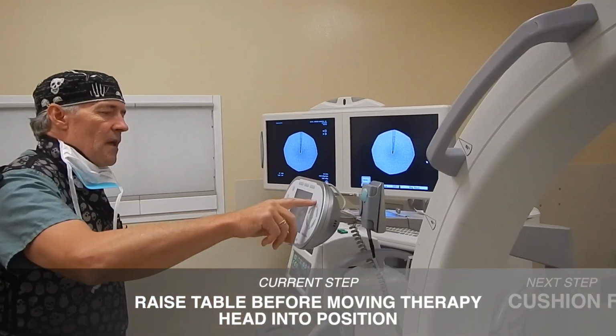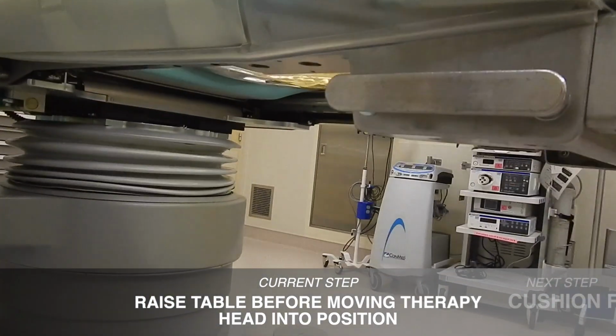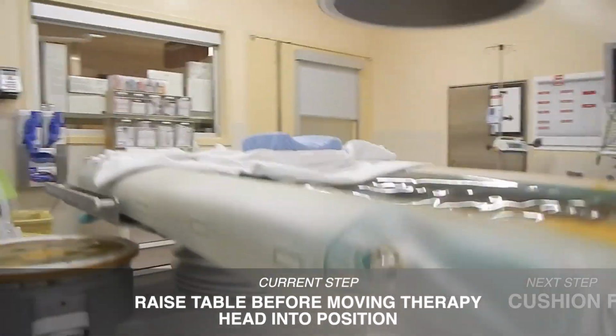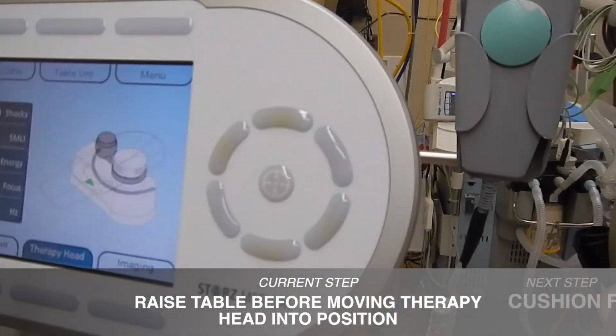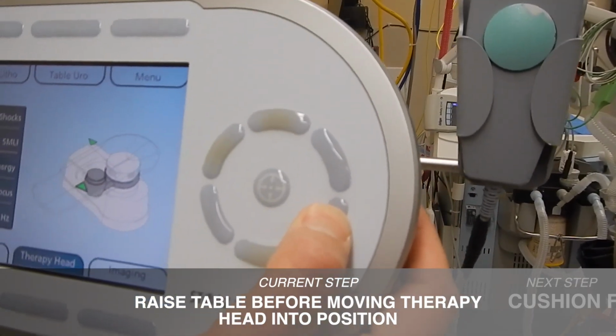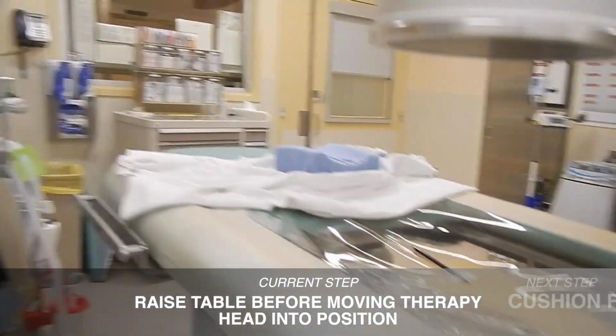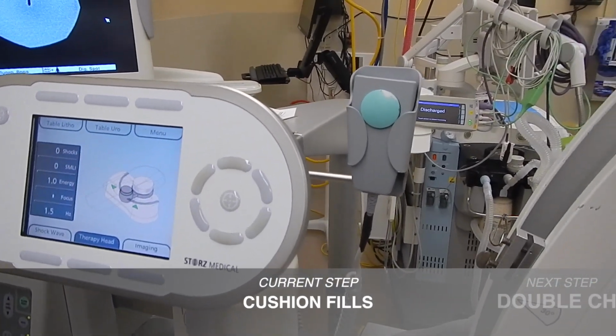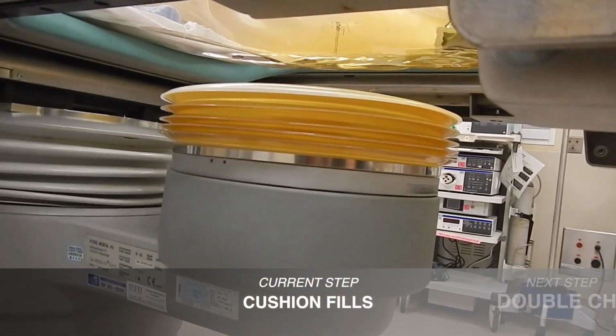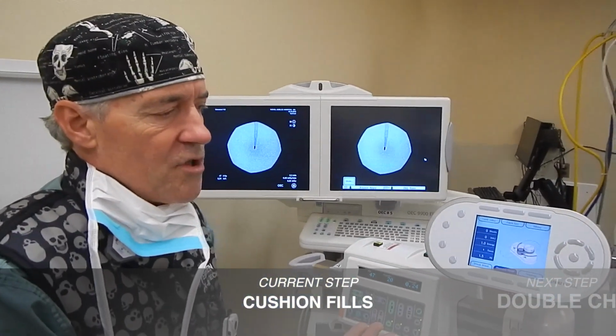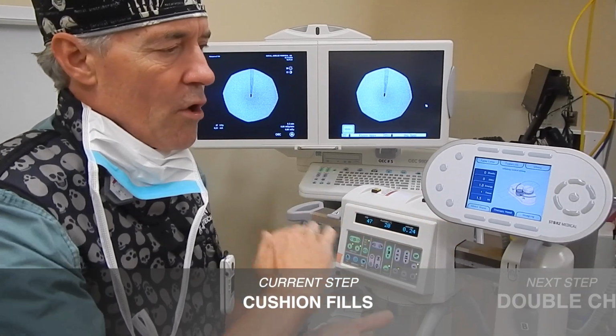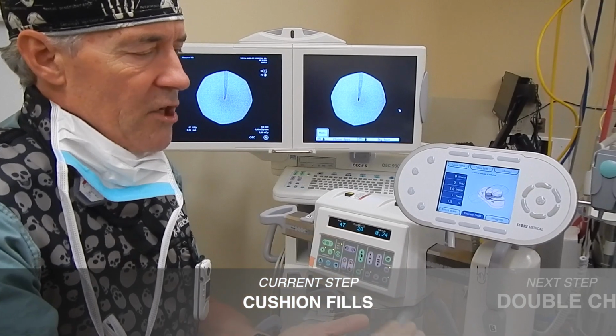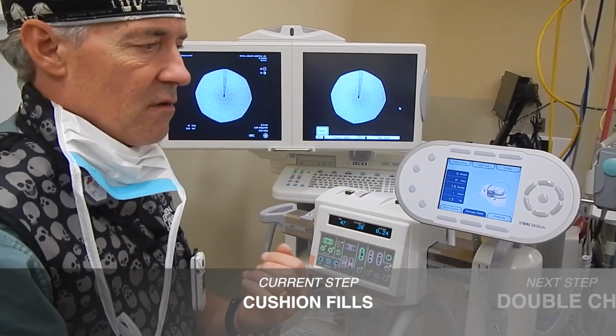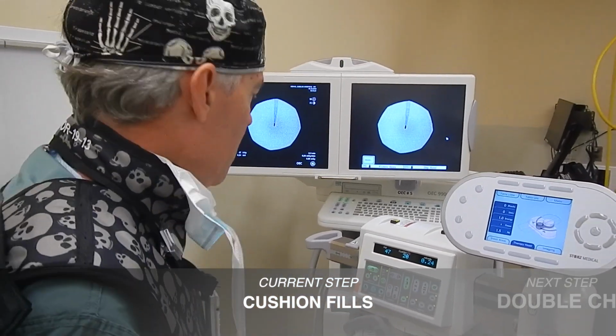So once that's done, then I raise the table, and if you watch as it goes up, it already happened, but there's a little pause, and that just means that it's gone high enough that the therapy head will now pass under without hitting anything. Not that it would ever hit anything. So therapy head, and we're going to put it back under, and wait for the sound, so we know it's in therapy position. Because we initiated the cushion filling earlier, it's filling up now. It's got a sensor that will sense the bottom of the table. It's just trying to adhere to the bottom of the table, and the oil causes a coupling effect. The water under the patient will enable the shock wave to pass through all that into the patient, into the stone that we're about to center.